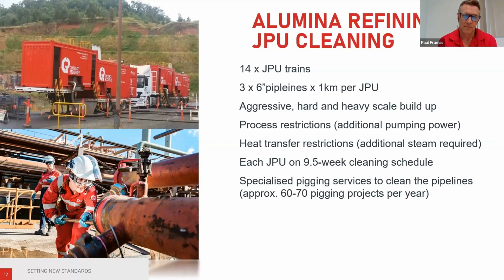In these pipelines, the scale build-up is extremely hard and aggressive, and it builds up very quickly. As that scale builds up, you need a lot more steam to get the heat transfer through to the product. Over time it becomes inefficient to run the pipeline more than around 9.5 weeks, which is what we've found. So each 9.5 weeks, the client takes those pipelines out of production, we clean them on a critical path program, and then put them back online and move to the next one - an ongoing project we do.